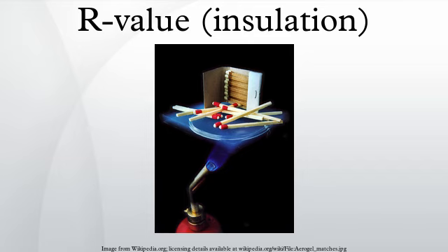Heat transfer through an insulating layer is analogous to adding resistance to a series circuit with a fixed voltage. However, this only holds approximately because the effective thermal conductivity of some insulating materials depends on thickness. The addition of materials to enclose the insulation, such as sheetrock and siding, provides additional but typically much smaller R-value.